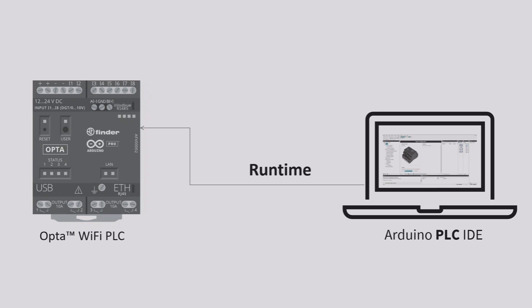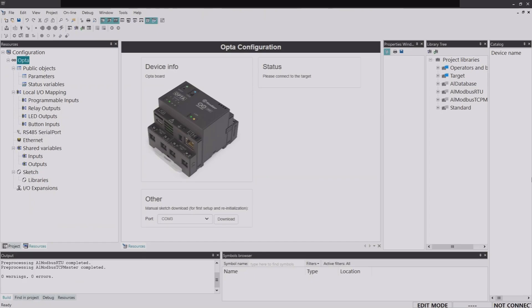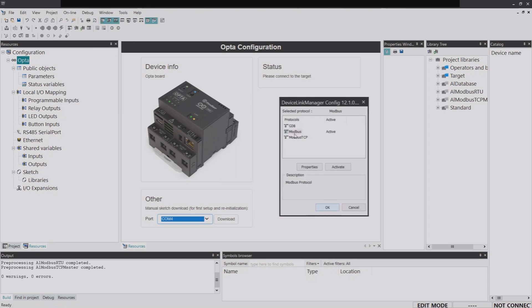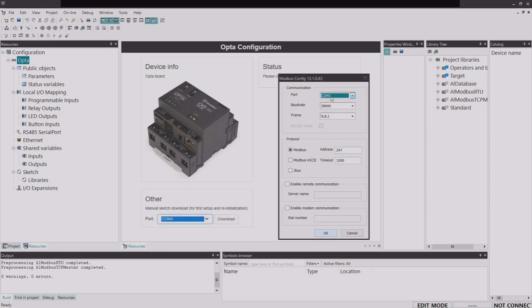To establish communication between the Opta PLC device and the software, the device needs to run a specific program called 'runtime' to interact with PLC IDE. In the Opta configuration window under 'Other,' you'll see multiple ports — select any one of them; I'll select the highest number. Make sure that port is not being used for Modbus communication: go to Online, click 'Set Up Communication,' click Properties under Modbus, and confirm the port there is a different number. As long as they don't match, click OK.